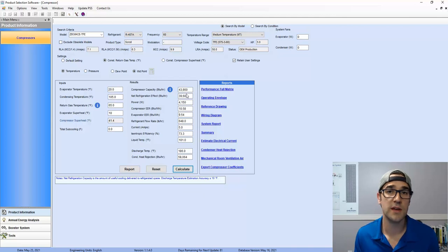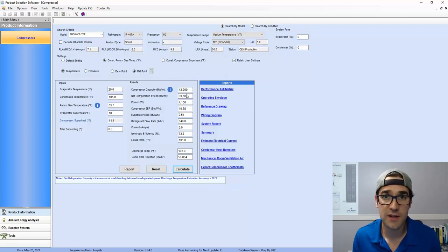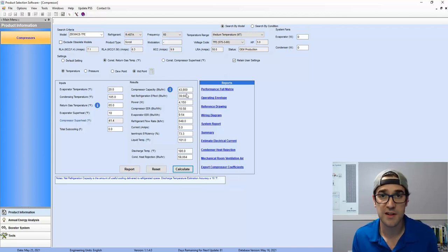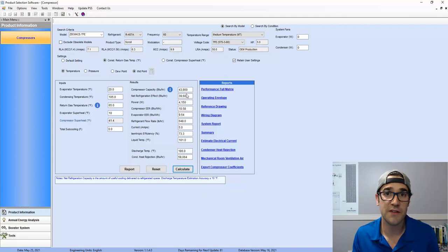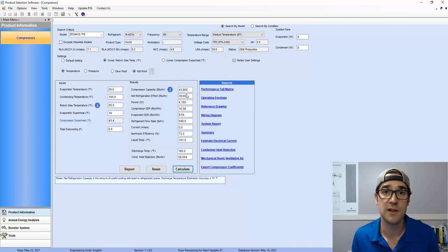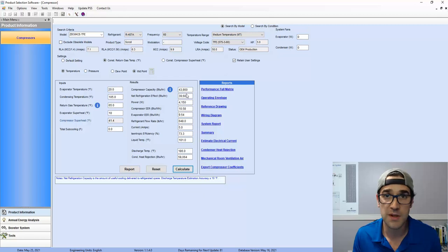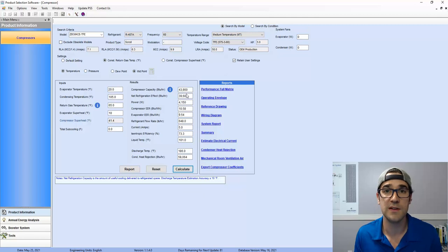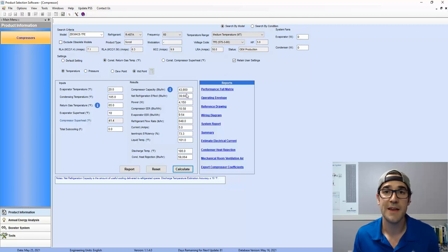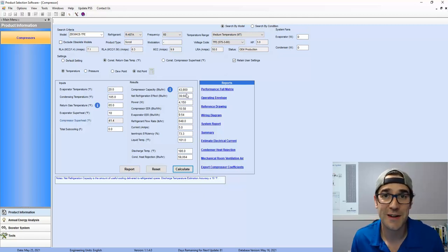So this is a quick video on it. I would love to hear your comments. If you use product selection software, if you size compressors, especially compressors using Glide, I would be using the midpoint sizing these compressors, not the dew point. My name is Trevor Matthews. Let's get a conversation going. Thank you.